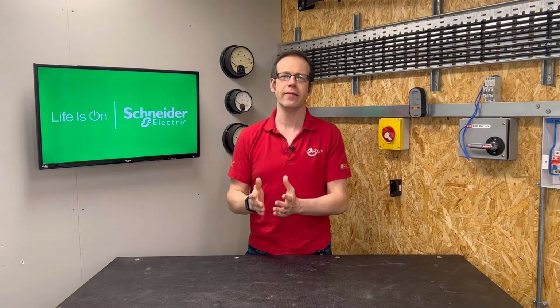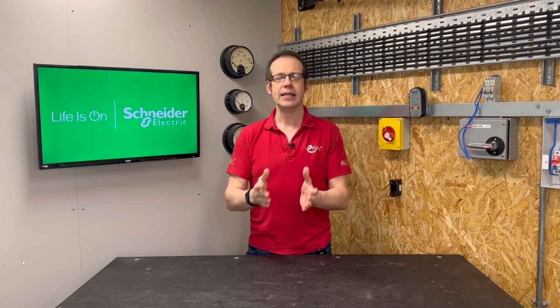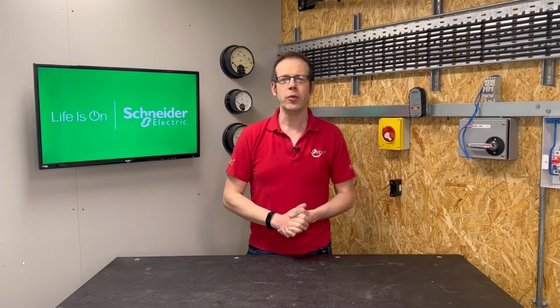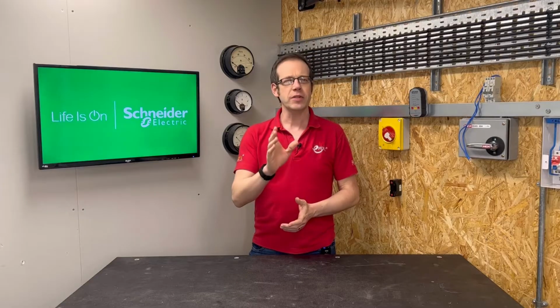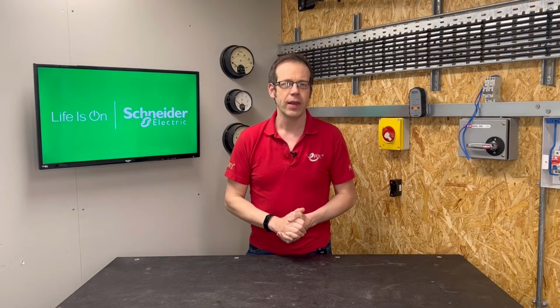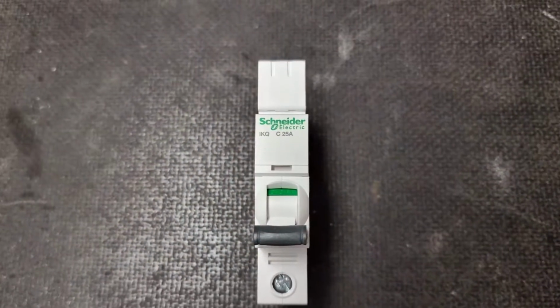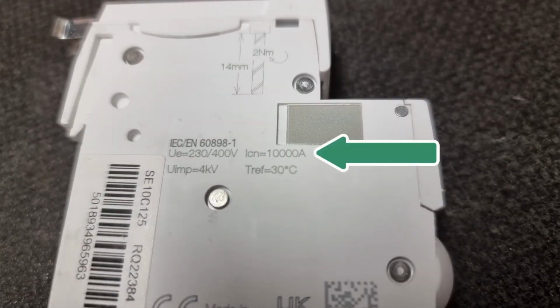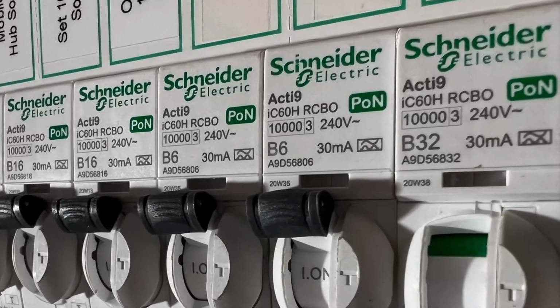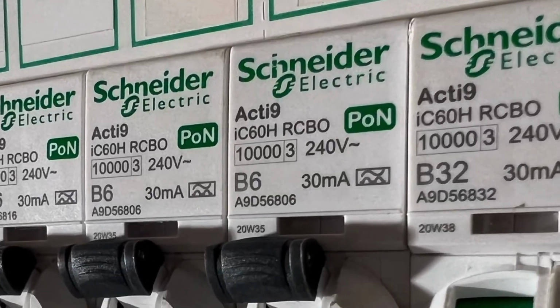Now, I'm sure you always look to fit the correct type and current rating of MCB, for example, B6, C20, B32, or whichever is correct for your circuit. But what's the other figure printed on there? On this circuit breaker from Schneider Electric, you can see the letters and numbers ICN 10,000 amps. On some, you will find the figure in a rectangle. So what exactly does this mean?